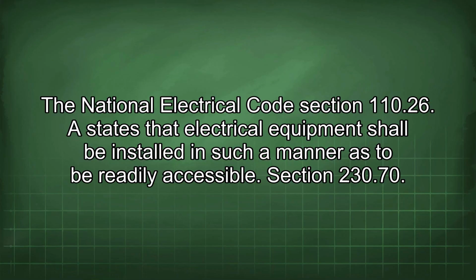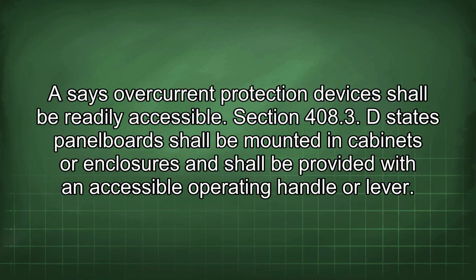The National Electrical Code's Section 110.26 states that electrical equipment shall be installed in such a manner as to be readily accessible. Section 230.70 says overcurrent protection devices shall be readily accessible.